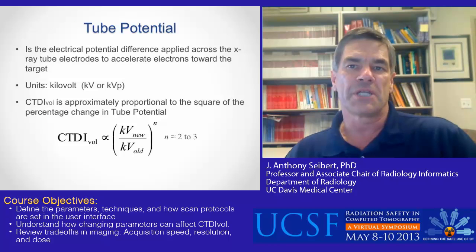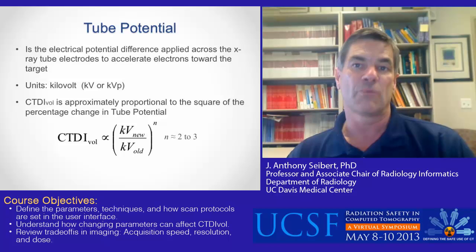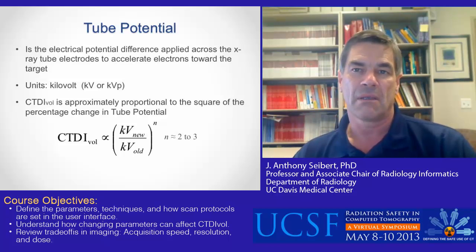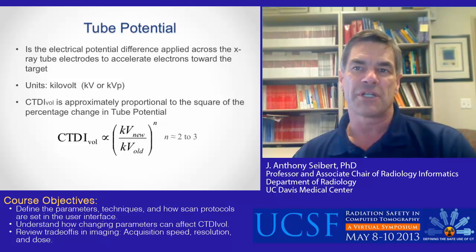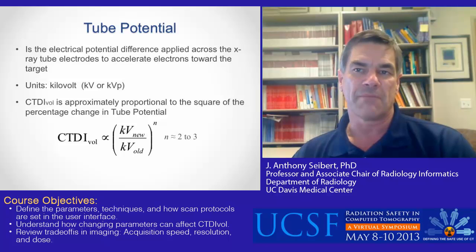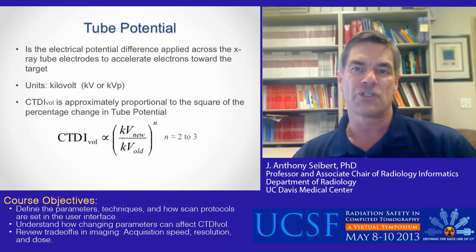The tube potential is the potential difference between the two electrodes in an x-ray tube, with units of kilovolt (kV) or kVp, where p indicates peak. Because x-ray production efficiency is higher at higher kV, the number of x-ray photons increases, as does the overall average energy of the x-rays produced and the number of x-rays transmitted through the body. The CTDI vol is approximately proportional to the ratio squared of the change in tube potential, with all other parameters fixed.